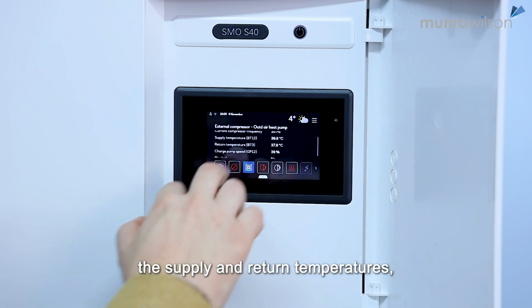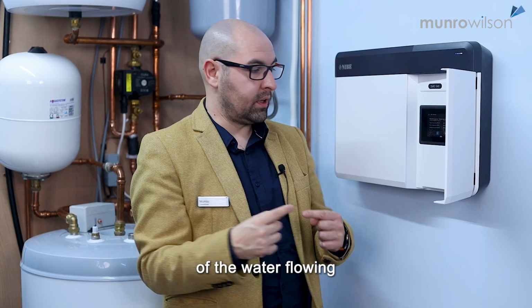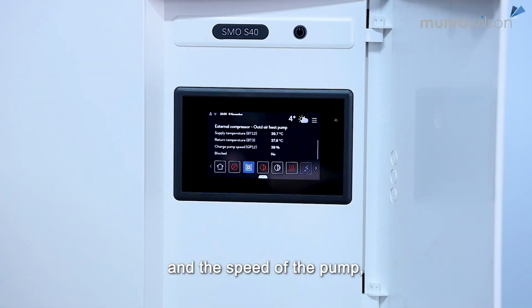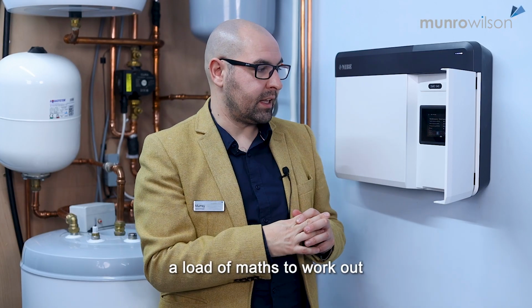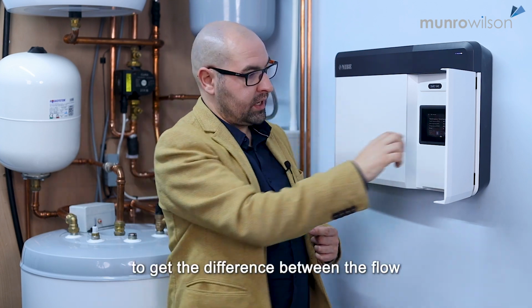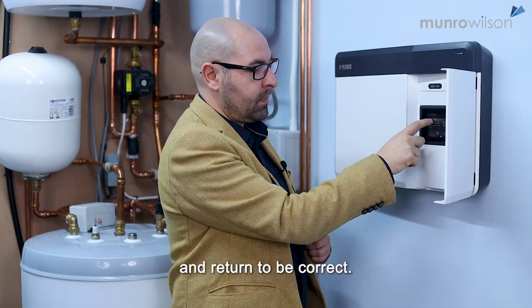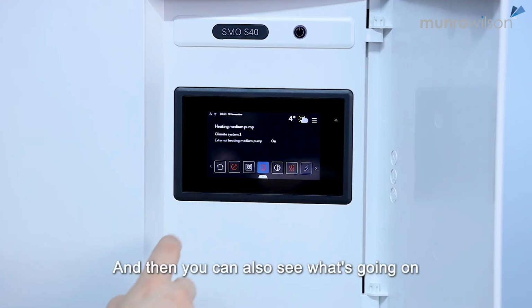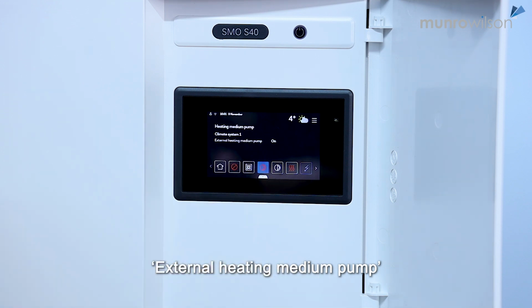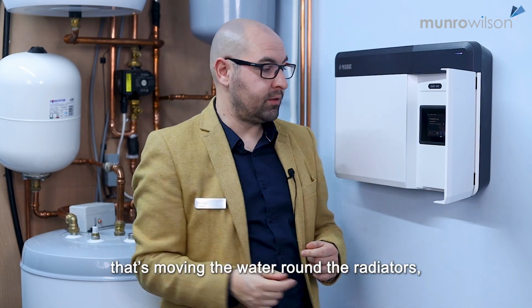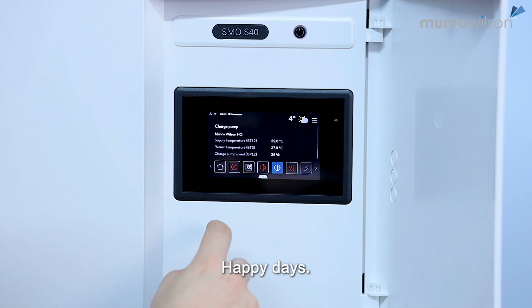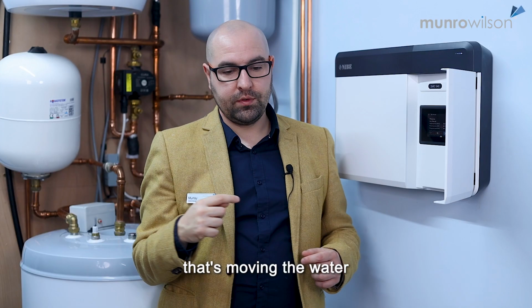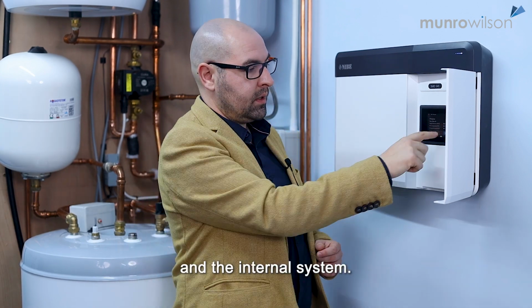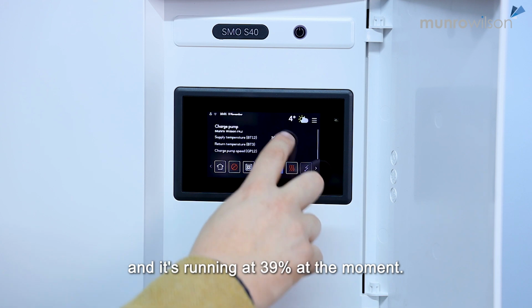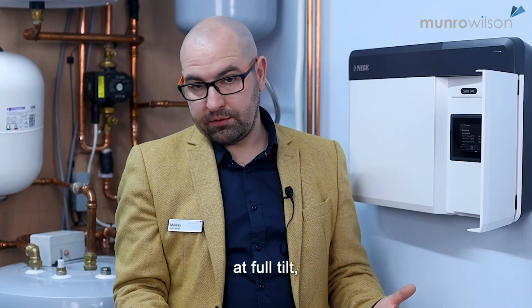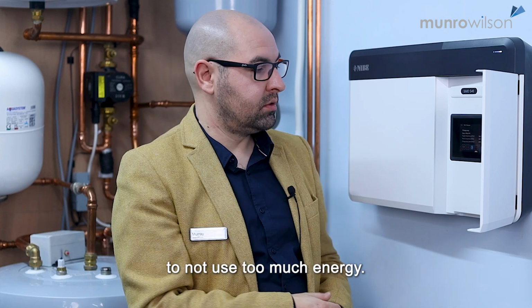And then we've got there again the supply and return temperatures, which are the temperatures of the water flowing around the radiators, and the speed of the pump, which is pumping them round, and the controller does a load of maths to work out what pump speed is needed to get the difference between the flow and return to be correct. And then you can also see what's going on with the pump. External heating medium pump, that is the fancy name for the pump that's moving the water around the radiators, and we can see that's on, happy days. And the charge pump is the one that's moving the water between the heat pump and the internal system, and it's speed controlled and it's running at 39% at the moment, which is good because we don't want to be running full tilt, we want to be running at a reasonable rate to not use too much energy.